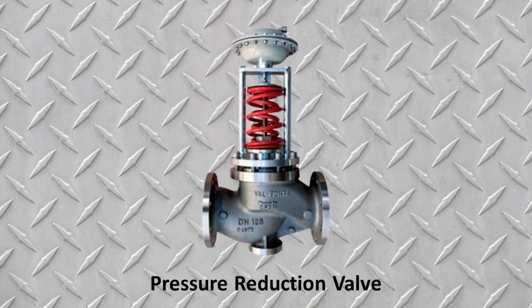In many cases, a plant will require two different temperatures for two different types of processes. You really don't need two different boilers. What you typically do is make steam at a high pressure in a single boiler, which would be the high temperature. And then you go through what we call a pressure reduction valve, or PRV, to knock the pressure down for part of the steam so that the temperature goes down with it. These PRVs reduce the pressure by going through a constriction, and so the energy content is not lowered. You do, however, make a lot of entropy and reduce exergy, for those of you just finishing a thermodynamics course.